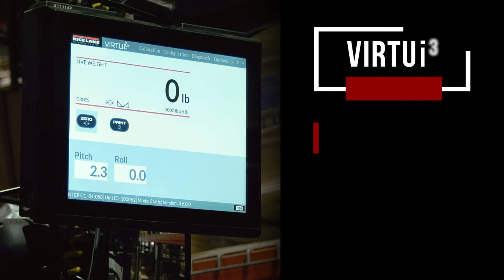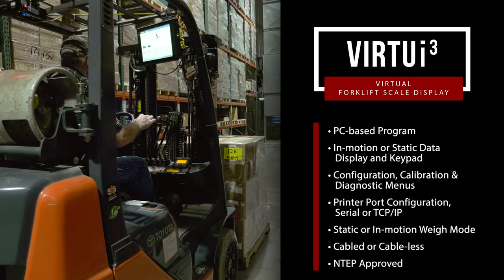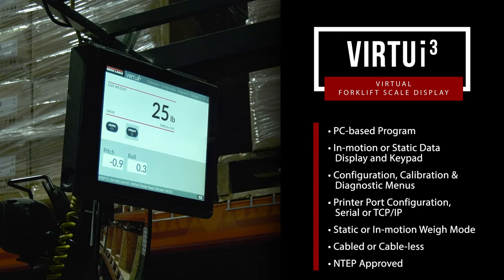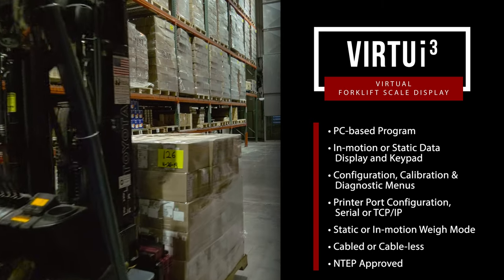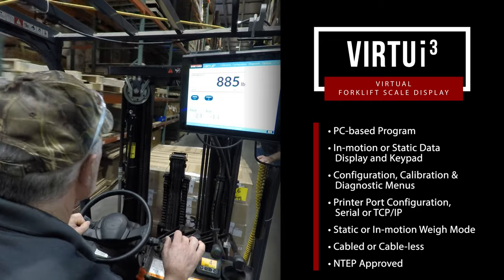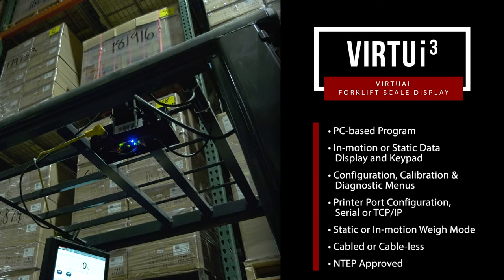For unmatched efficiency, the VIRTUi3 virtual solution utilizes a mobile device or PC in place of a traditional weight indicator. When configured for in-motion use, VIRTUi3 captures and holds a legal-for-trade weight, eliminating the need to stop and capture a stable weight for each pallet. For connection to peripheral equipment, RS-232, USB, or Bluetooth connections are available.